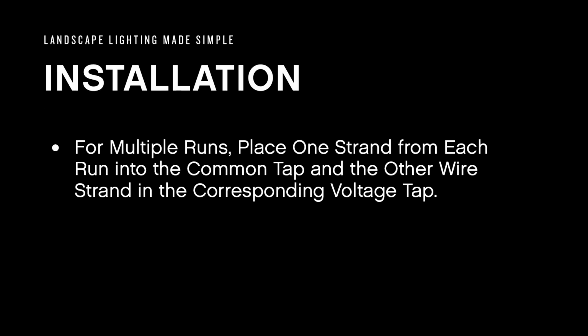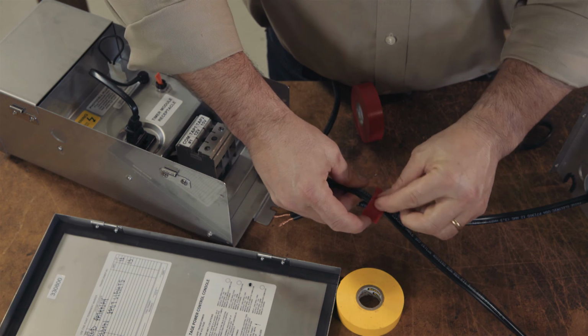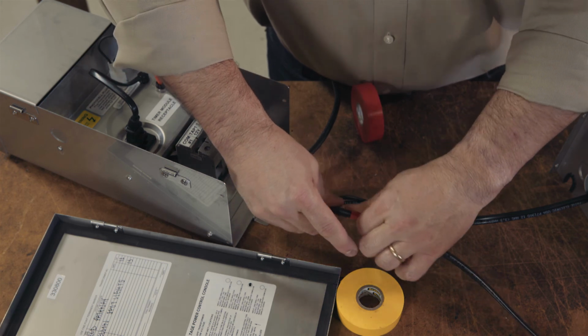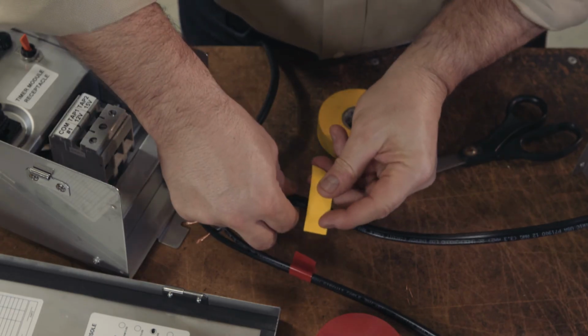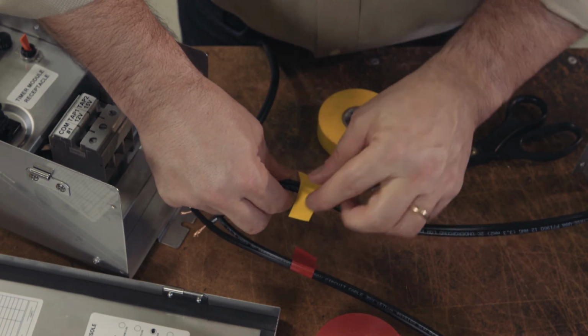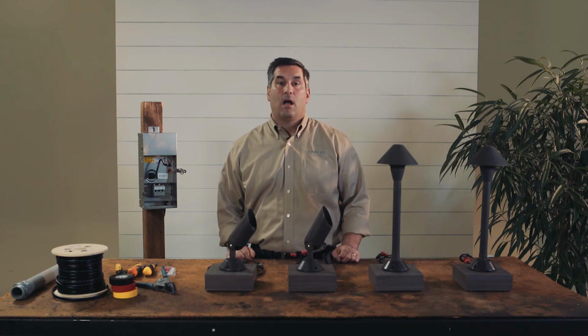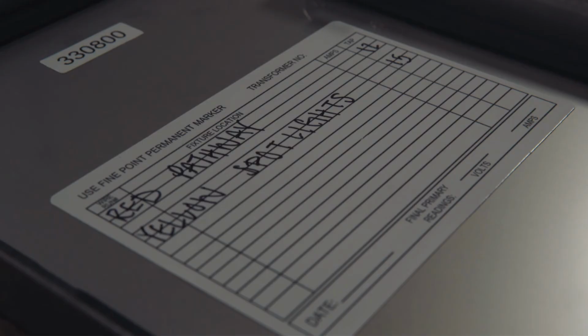If you have multiple runs into the transformer, follow the same procedure, only place one wire of each strand into the common tap and the other wire strand in the corresponding voltage tap, dependent on the length of run. Always identify each cable entering the wiring cavity. Mark each individual wire and identify the cable run on the inside of the transformer door. Colored electrical tape works well to identify each individual run.